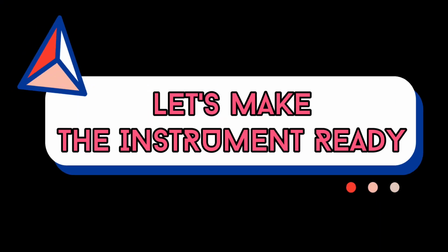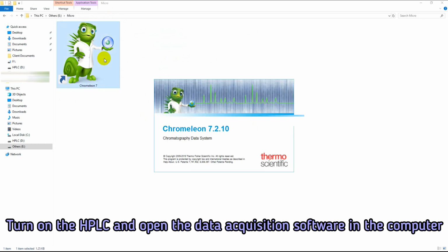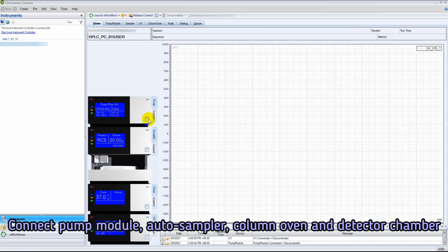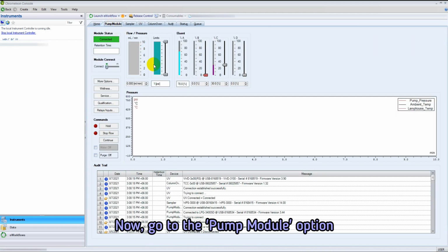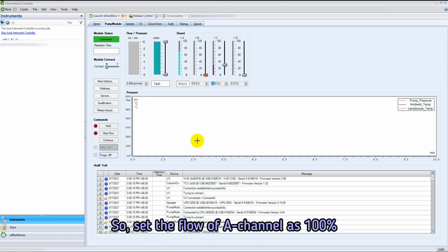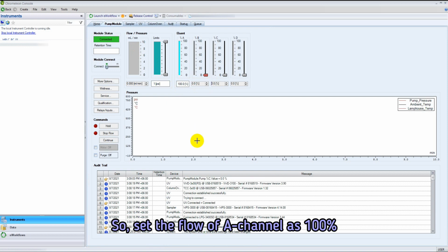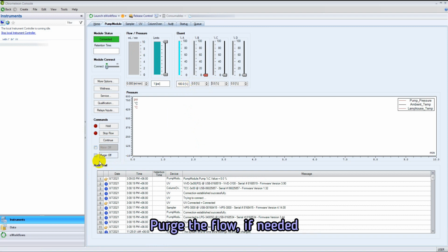Let's make the instrument ready. Turn on the HPLC instrument and open the data acquisition software in the computer. Connect pump module, auto sampler, column oven, and detector chamber. We kept mobile phase in A channel, so set the flow of A channel as 100%. Set the flow rate at 1 ml per minute. Purge the flow if needed.